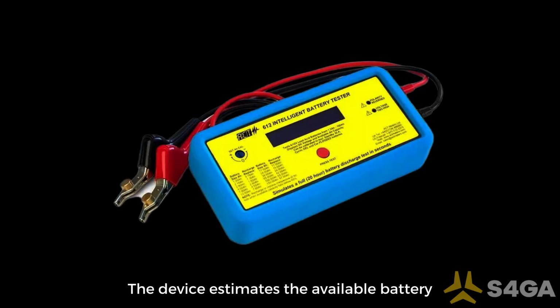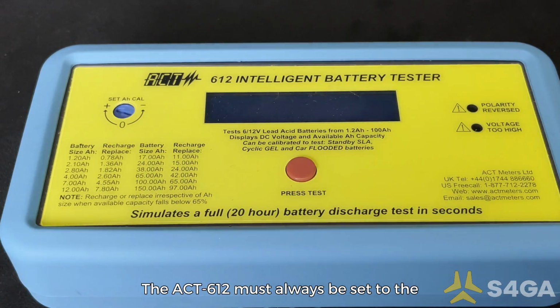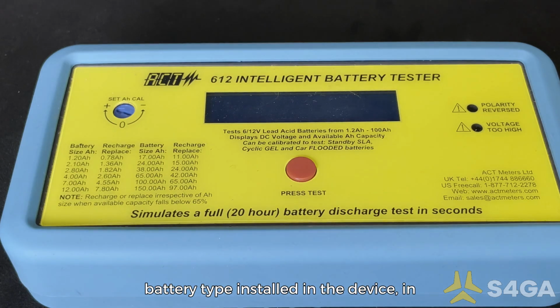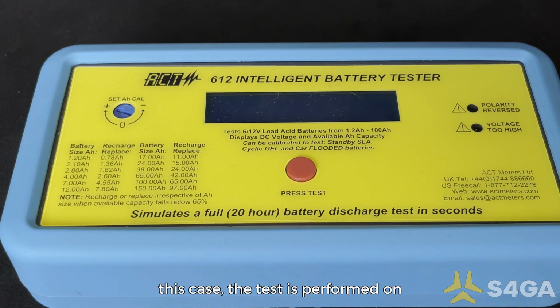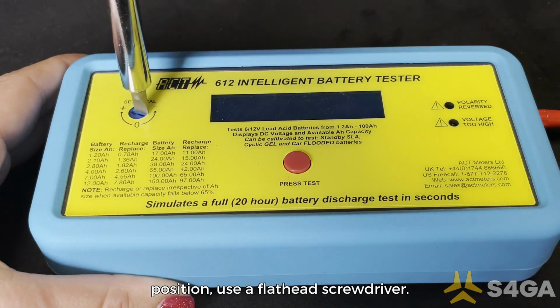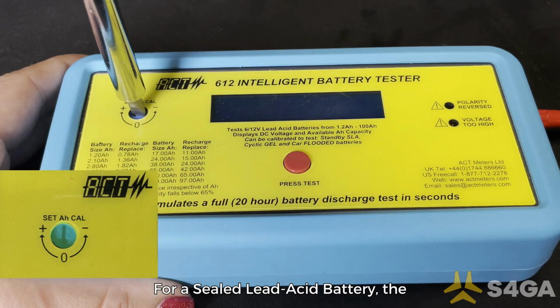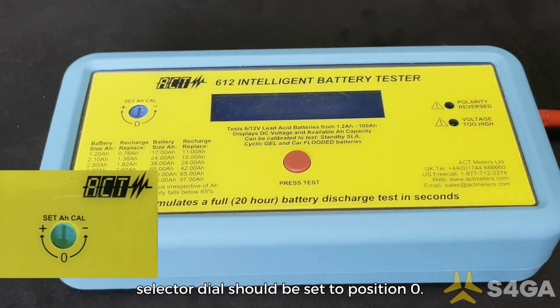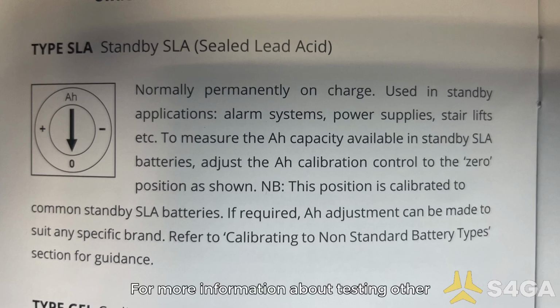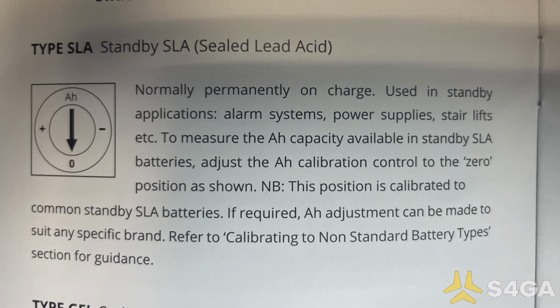The device estimates the available battery capacity in ampere-hours, allowing fast evaluation of the overall battery condition for maintenance and diagnostic purposes. The ACT612 must always be set to the battery type installed in the device. In this case, the test is performed on a sealed lead-acid battery. To set the selector dial to the correct position, use a flathead screwdriver. For a sealed lead-acid battery, the selector dial should be set to position 0. For more information about testing other types of batteries, please refer to the ACT612 Battery Tester User's Manual.